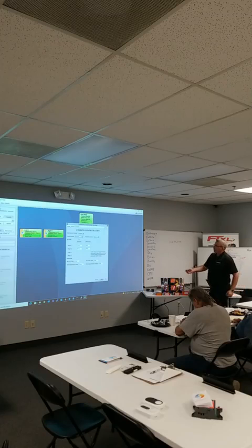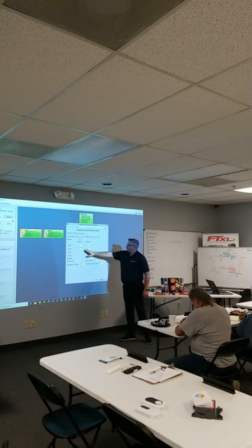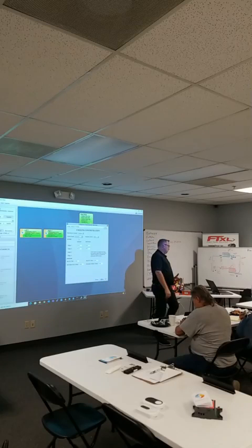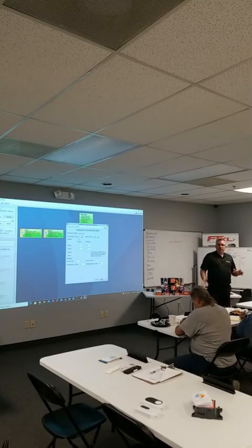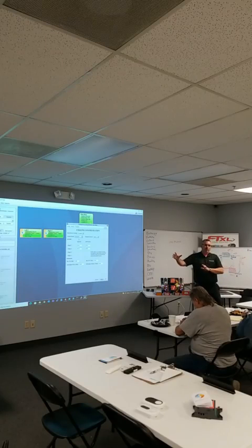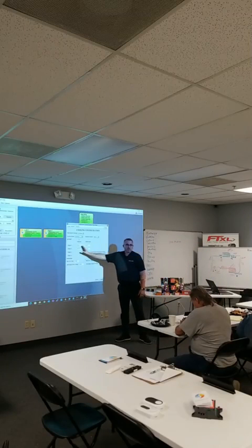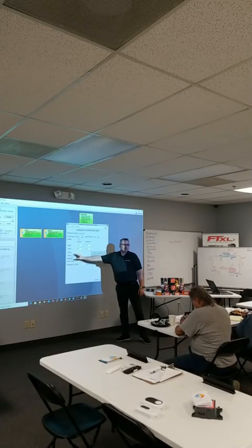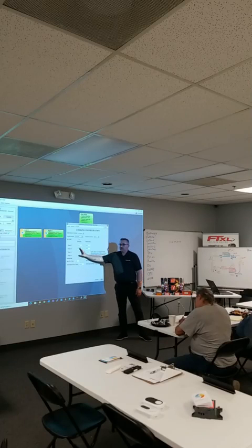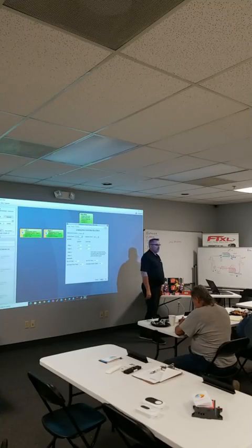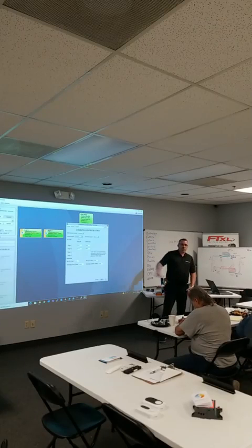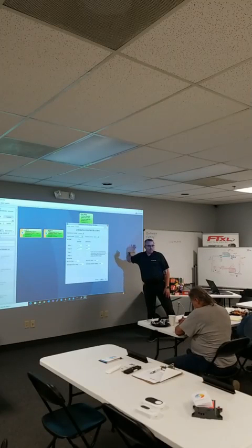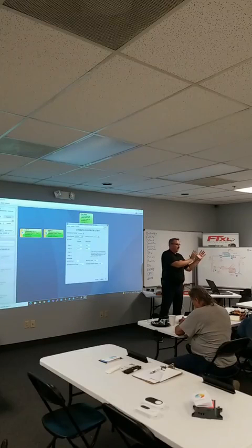Even if this was a constant volume unit, we still use that hysteresis relay for turning the outputs on and off. Sometimes I've heard scenarios where guys say, there's a really small unit, and because it's small, if I let it swing out that far, I'll lose the space. So in that instance, they'll say, when I get just a little bit of a cooling demand, I'm going to start the compressor. Or they'll say, when stage 2 kicks on, it's kicking on too early and it's way overcooling the space. What we're giving you is the freedom and the flexibility to move when you start those stages.